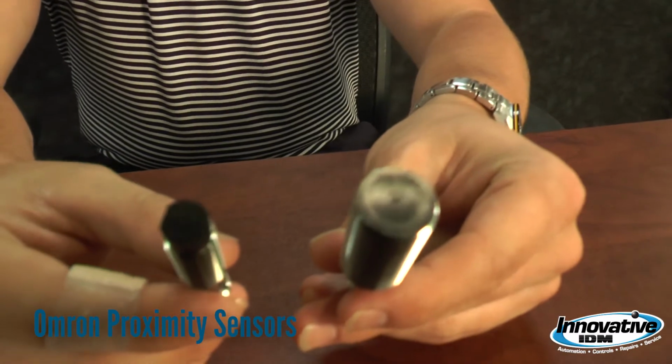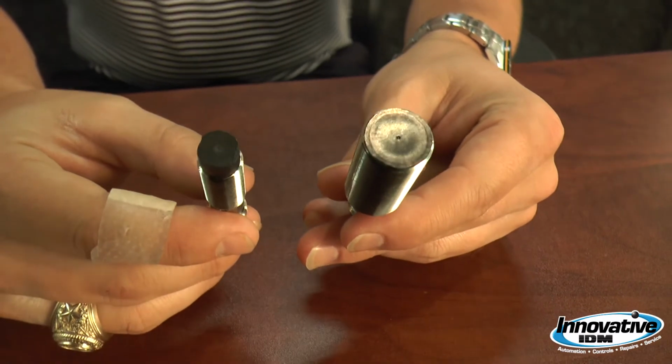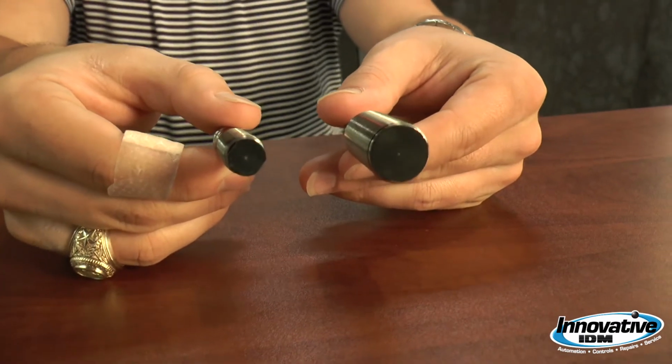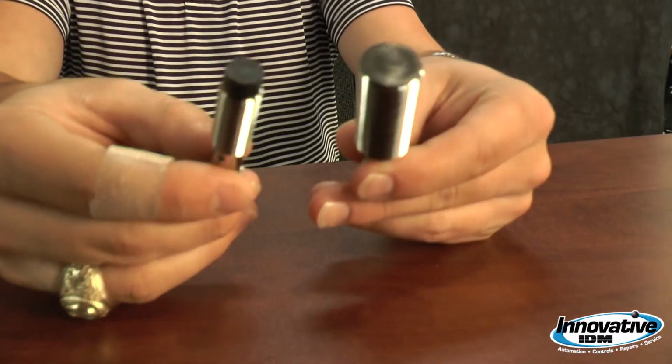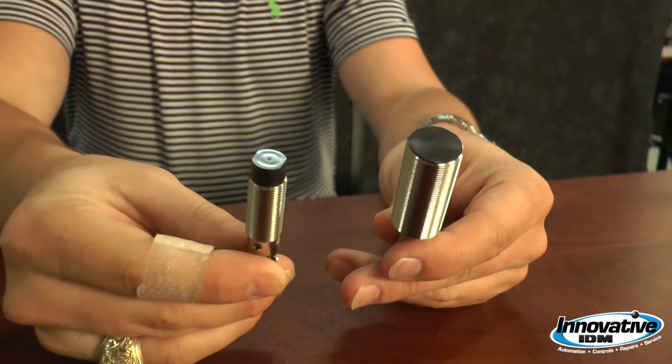What I have here are a shielded and an unshielded inductive proximity sensor. You can easily tell the difference between the two because a shielded proximity sensor will have metal threads that run the entire length of the body, while an unshielded version does not. Now, what you need to know is when and where you will use either one of these options. An unshielded inductive proximity sensor is going to have a greater sensing distance than its shielded twin. A greater sensing distance might be beneficial to you in your application, however, because of the way that these sensors are mounted, an unshielded version might not be the best thing for you.